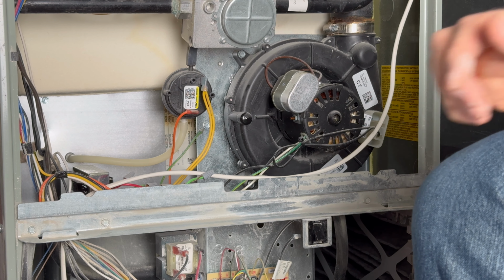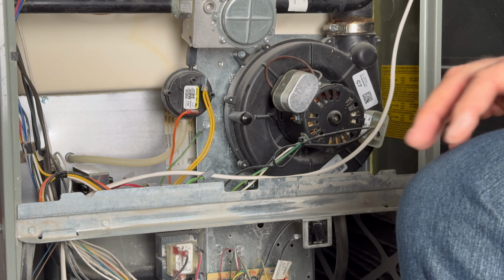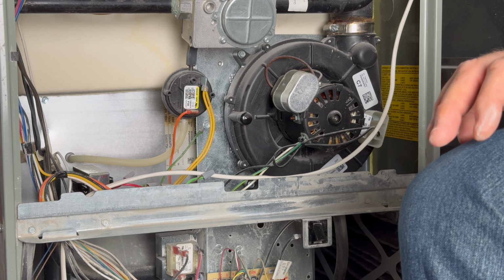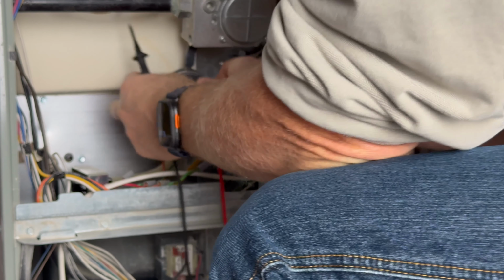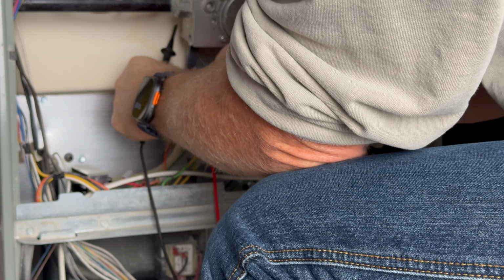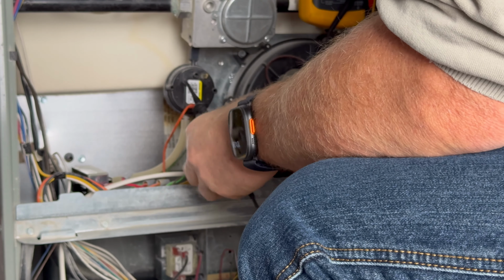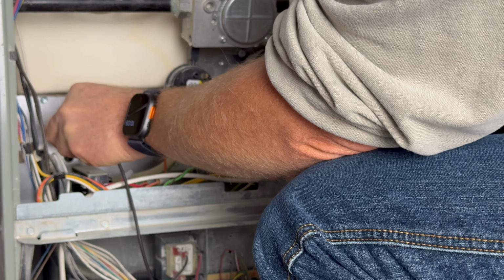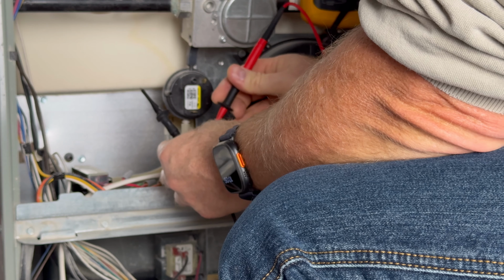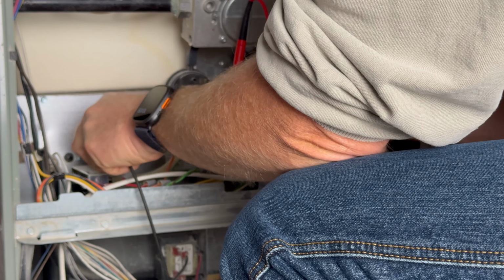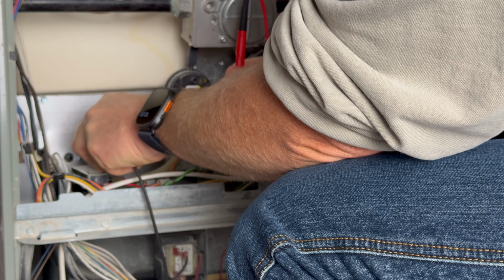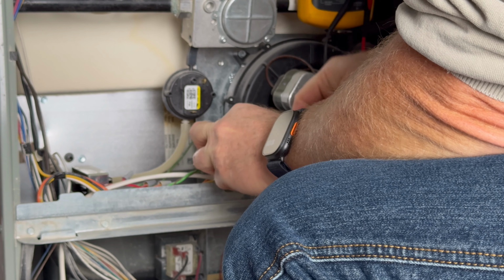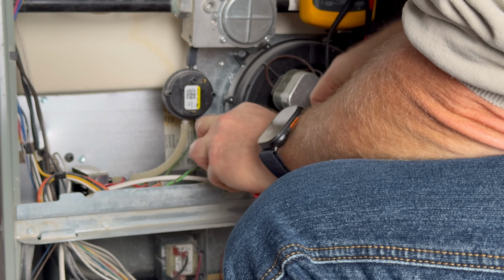I'm not sure at this point if my pressure switch is bad or if there's a flow obstruction in the system somewhere, so I'm going to take it apart and check it out. I've turned off the service disconnect, but never trust an electrical circuit unless you've checked it with a meter yourself. I'm checking for AC voltage on the yellow leg to ground, then the orange leg to ground, and finally, I'm checking orange to yellow because that would show AC voltage if this is an ungrounded control circuit.